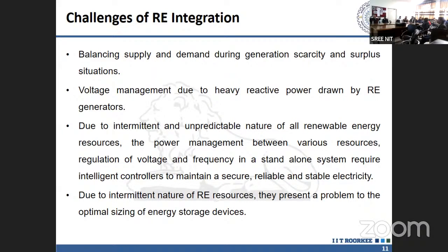But if the supply is there and load is being supplied, what happens in the daytime? Normally the load is very high in the educational institute itself, but in the off time, when the offices are off, all office ACs are off. In the hostel, no AC is provided, so there's a simple load. So what happens? The voltage rises very high, and many of the equipment has burned.